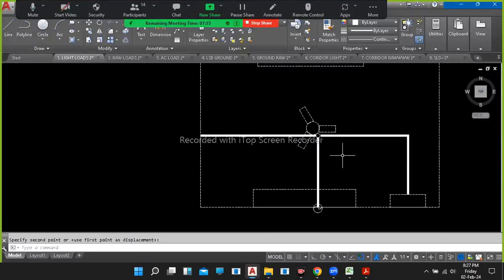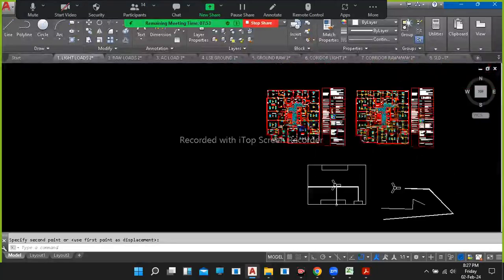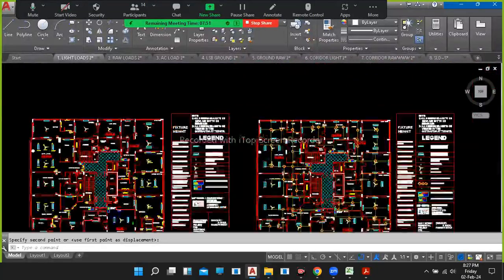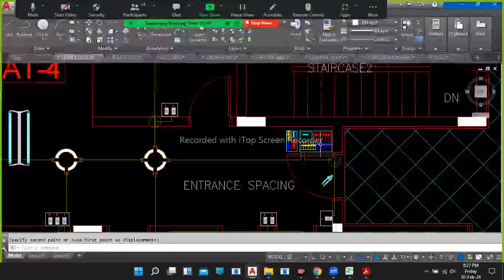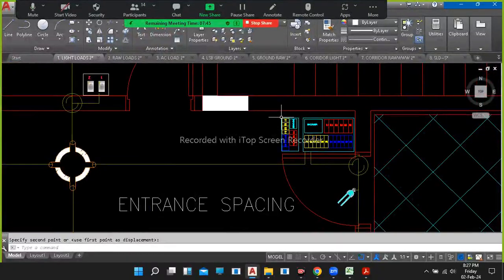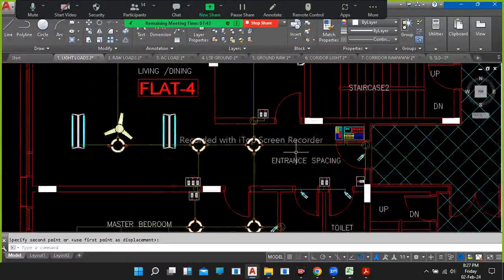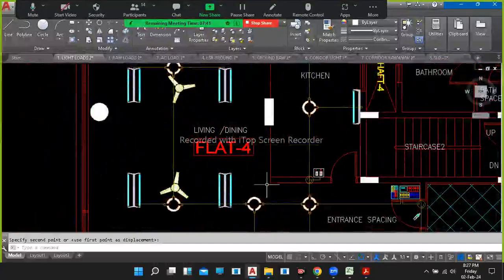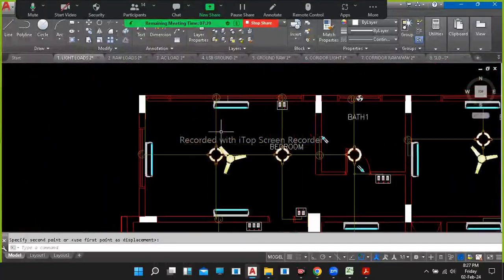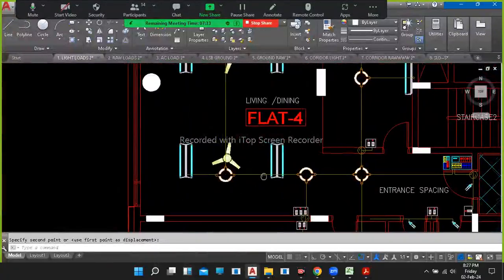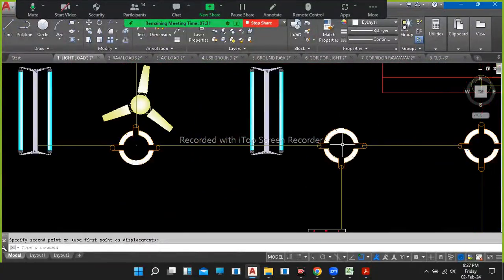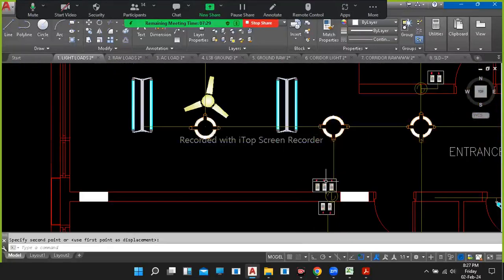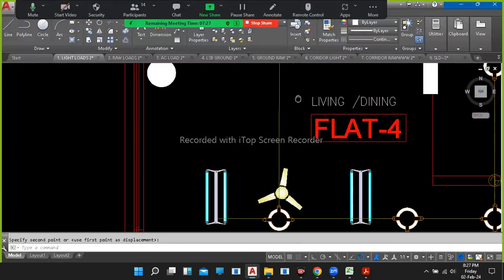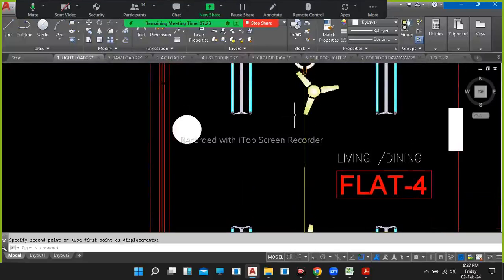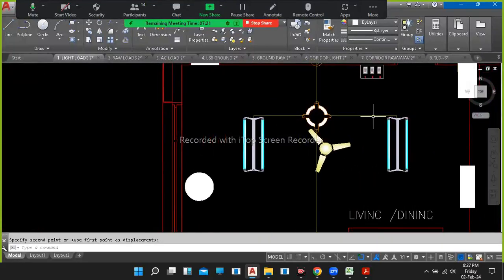Yes sir. So now for the conduiting work, from the distribution board (DB), first make sure the main center conduit runs through all the rooms. Then from that same center conduit, I take the tapping to the switchboard, and from the switchboard the same conduit routes to all the points.